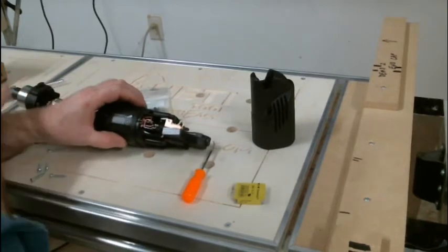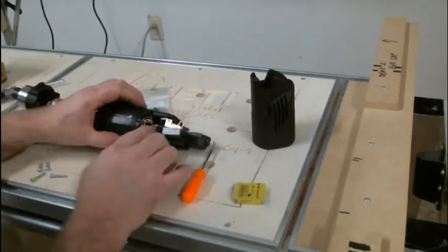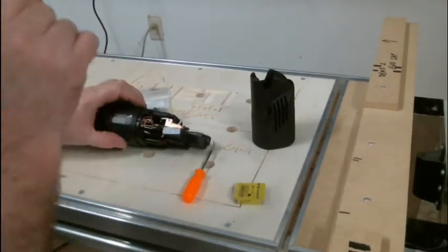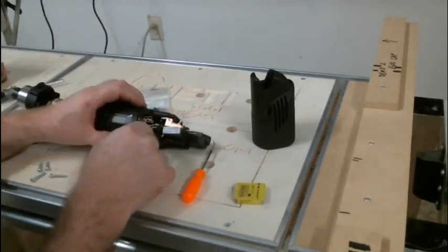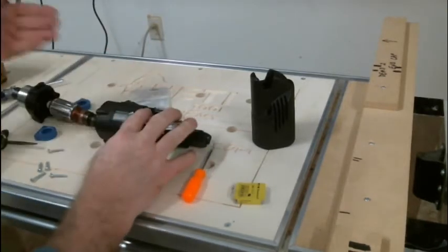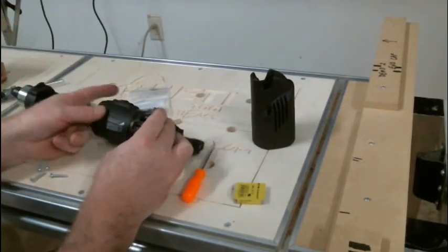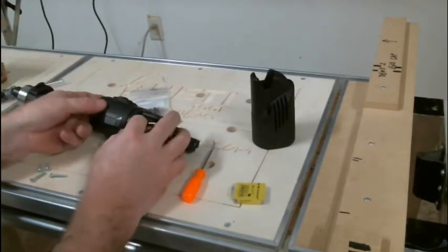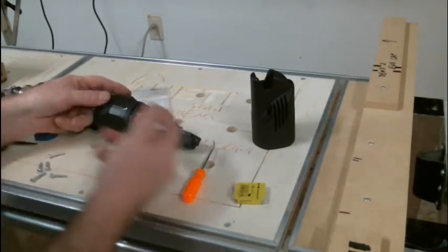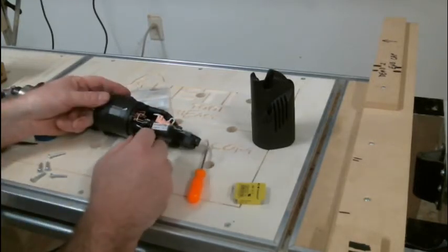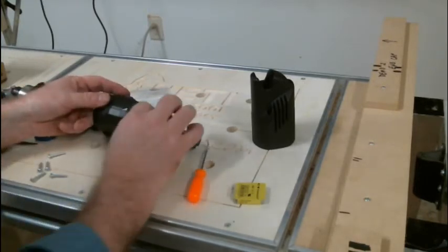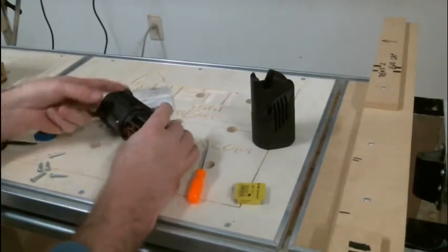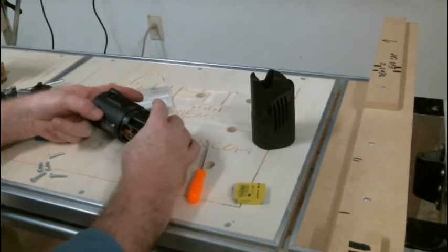You'll find that when you're putting this back in, if you leave the brushes in, the springs are going to be pushing the brushes down. They're going to block off the ability to get the shaft all the way back in. So you either want to pull them all the way out when you do the replacement or just back them off as it's coming in.